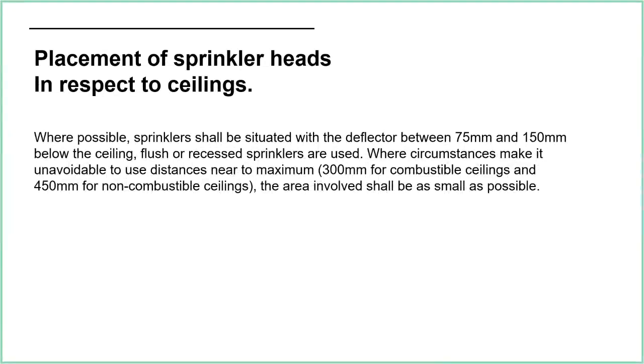Where beams make it difficult to place heads at 75–150mm, we have to use different methodologies. There are extended rules: up to 300mm for combustible ceilings and 450mm for non-combustible ceilings. However, there is a clause — the area involved shall be as small as possible. This shouldn't be done just because it's easier or quicker; there must be a good structural reason for extending those distances.